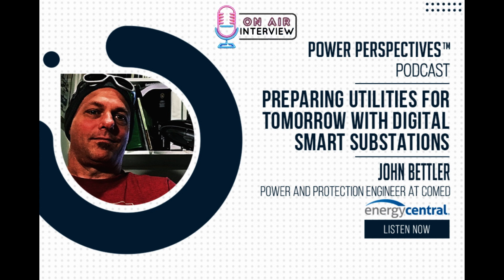The next thing would be sample values. So I'm a relay and I'm taking in currents and voltages into my relay. 66.4 volts nominal would be for voltage, and let's say 5 amps nominal for current. I'm taking this in. Since I'm a microprocessor relay, what I'm doing is digitizing it. I'm taking those analog quantities and turning them into some digital quantity so that my relay can then process it. Because otherwise, you can't just take 66 volts and apply it to a chip and blow it up.